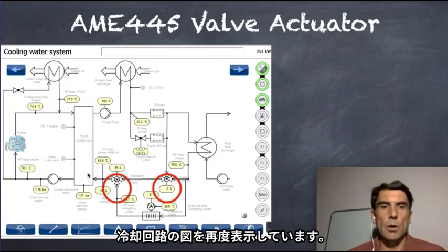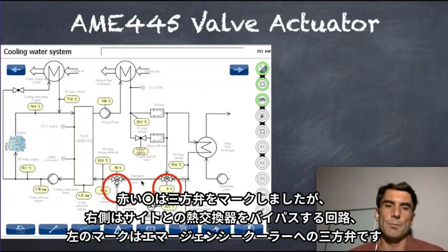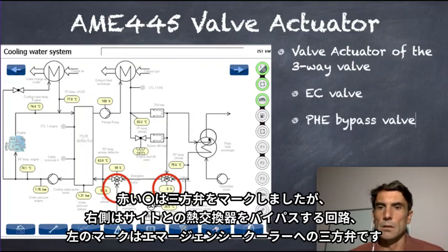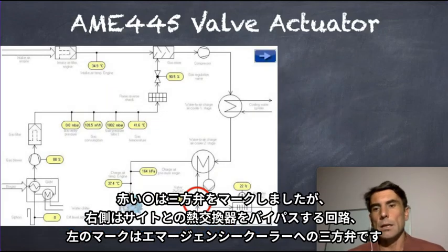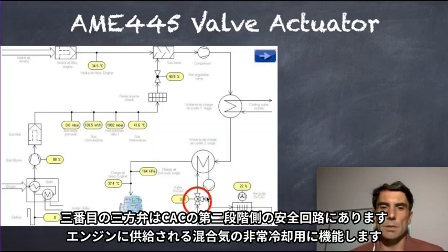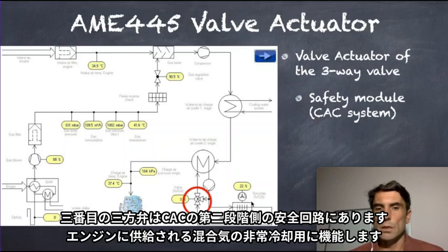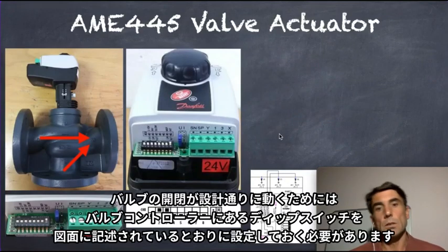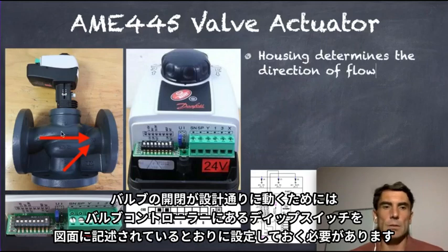We have here the flow diagram of the heat transfer unit again. We have here the bypass valve, this is bypassing the plate heat exchanger, and we have here the emergency cooler valve, this is for that cycle. The third one, what I mentioned already, is from the safety module, the charge air cooler second stage. It's connected to the charge air cooler to cool down the gas that is going through, and to the radiator cooler on the water side. So the same is for all these actuators and valves.